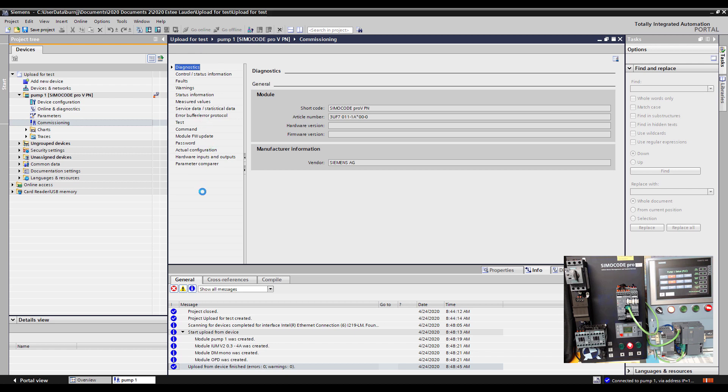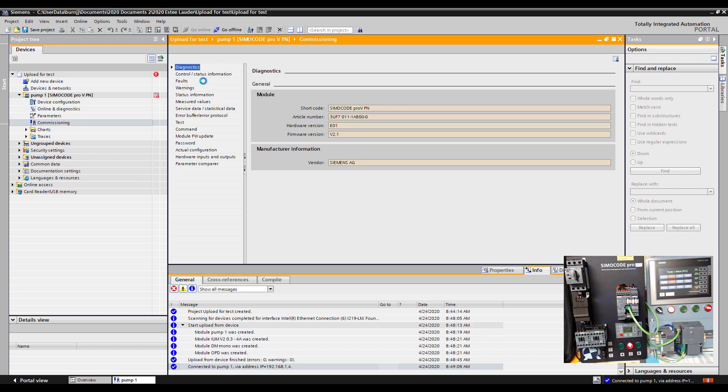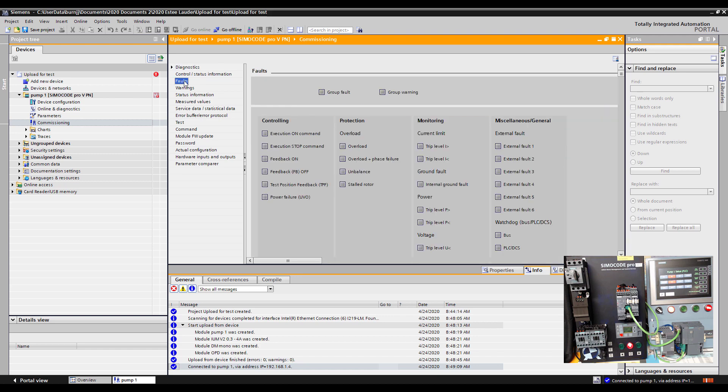Once it's completely online I'm going to come in here and select faults. And you'll see here we've got a group fault but specifically what has happened, I've had an overload condition. So basically I had too much current for too long of a time frame and the motor tripped out on an overload.